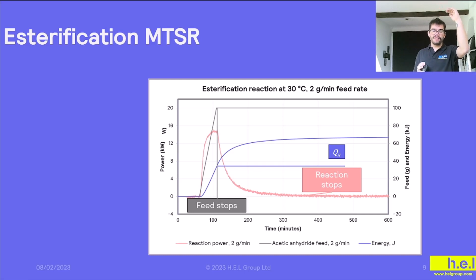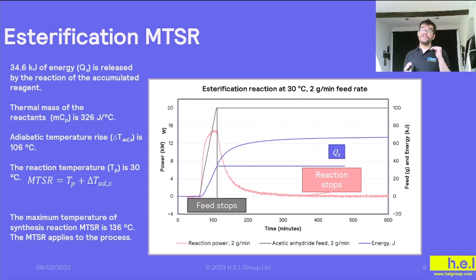So we have the measuring of heat that we had when we stopped the feed, and then we can calculate the difference between this value and the maximum value of the accumulated heat. And in this experiment that is going to be 34.6 kilojoules of energy, and we know because of the calorimetry that also our reactants' thermal mass is going to be 326 joules per centigrade. The adiabatic temperature is going to be then 34.6 times 1000 divided by 326, and it's going to be 106 degrees. Then if we add that to the 30 degrees, which is the temperature of our reactor, we're going to have a total accumulation of 136 degrees Celsius.